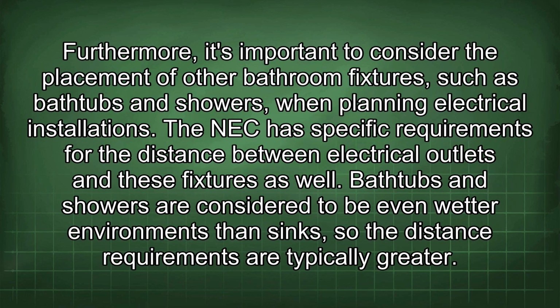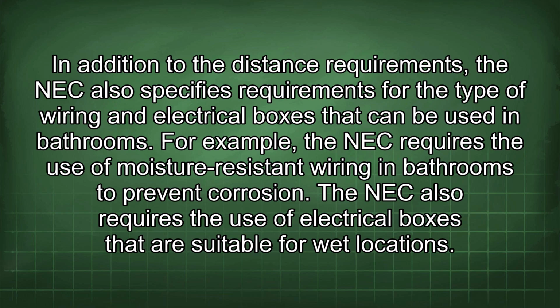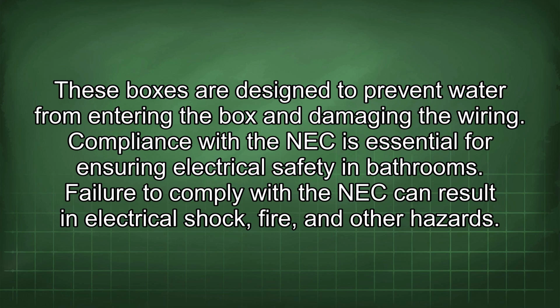Furthermore, it's important to consider the placement of other bathroom fixtures, such as bathtubs and showers, when planning electrical installations. The NEC has specific requirements for the distance between electrical outlets and these fixtures as well. Bathtubs and showers are considered to be even wetter environments than sinks, so the distance requirements are typically greater. In addition to the distance requirements, the NEC also specifies requirements for the type of wiring and electrical boxes that can be used in bathrooms. For example, the NEC requires the use of moisture-resistant wiring in bathrooms to prevent corrosion. The NEC also requires the use of electrical boxes that are suitable for wet locations. These boxes are designed to prevent water from entering the box and damaging the wiring.